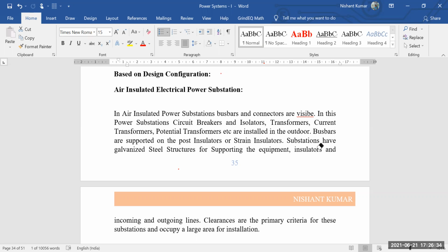Substations have galvanized steel structure for supporting the equipment, insulators, and incoming and outgoing lines. Clearance is the primary criteria for these substations, and they occupy a large area for installation, so we could categorize this as an outdoor segment.